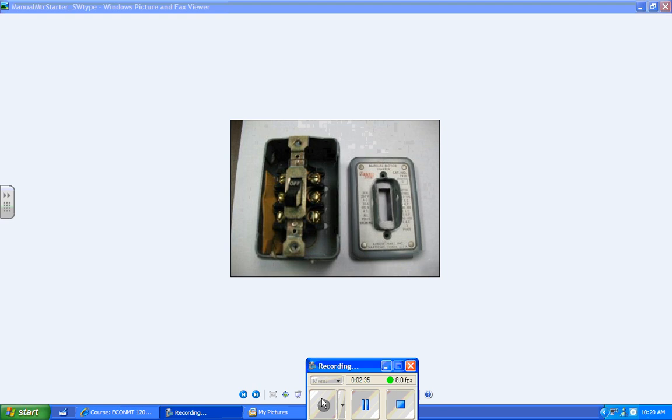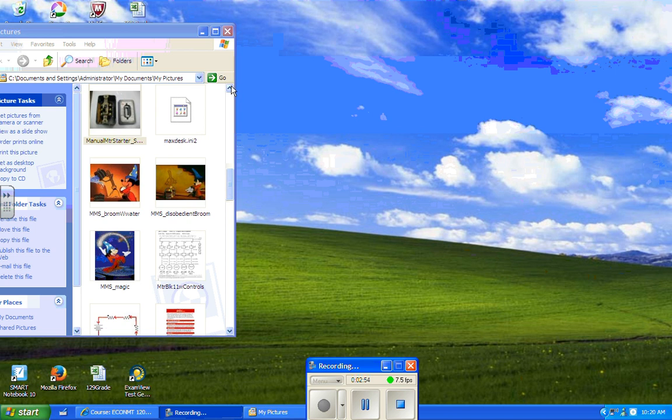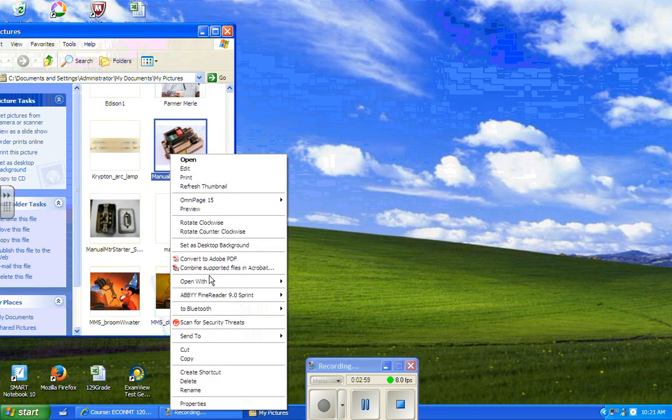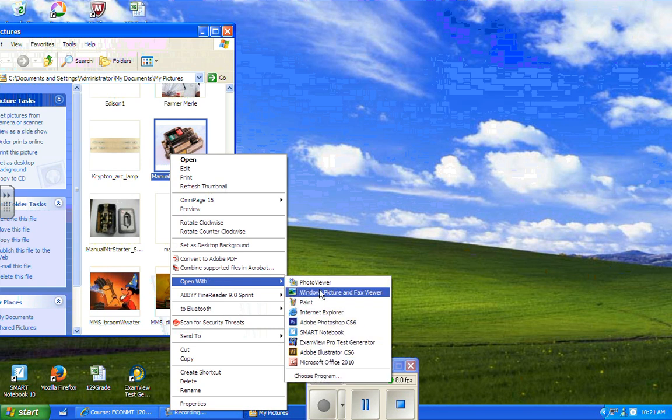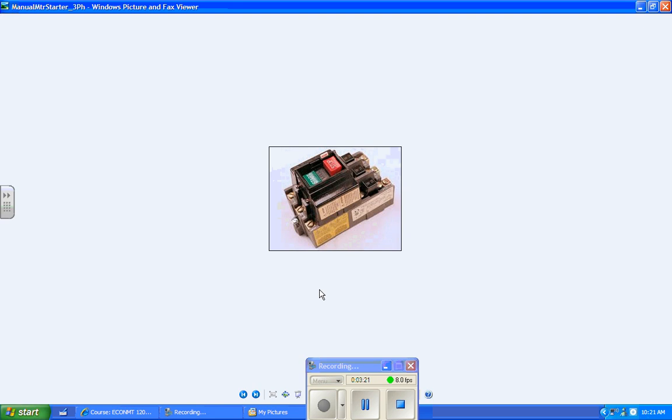Now the little handle switch is not the only kind of manual motor starter. This little starter right here is another kind where it's still push button. It's got a start and a stop, and again it's not magnetic. It does not have a coil that holds it in. Once you've hit start, it's mechanically held by a latch.